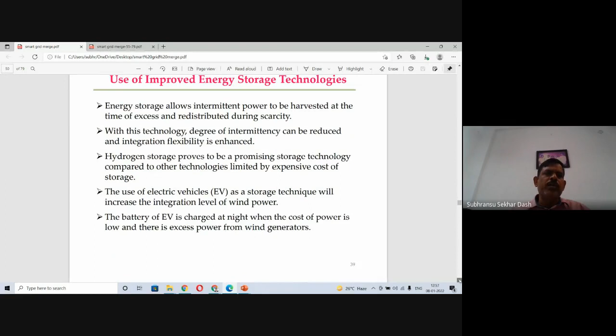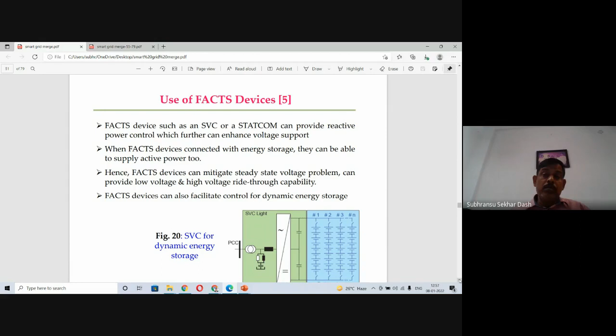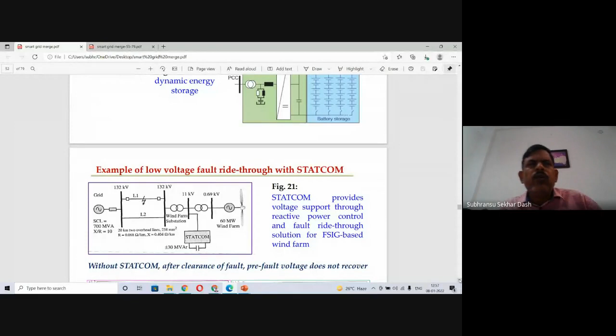Use of facts devices - as I've already told you, SVC, STATCOM, or similar devices can be used so that they can supply reactive power and even real power. That is a very important thing. One example is low voltage fault ride-through using STATCOMs.